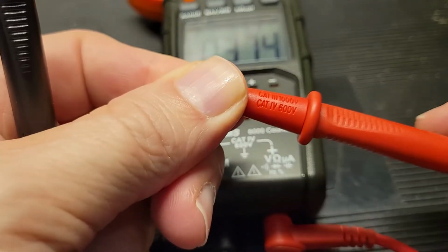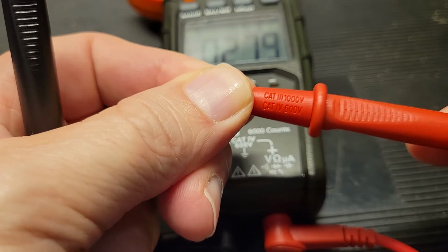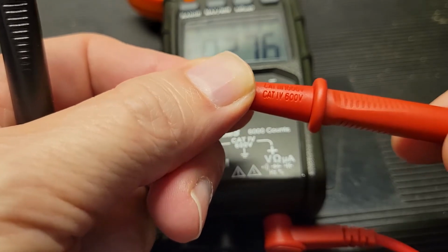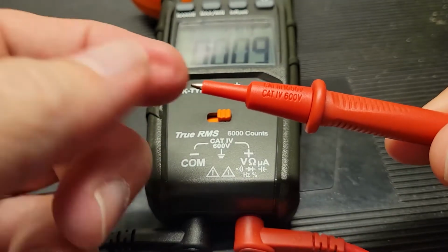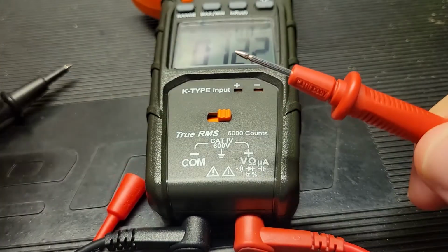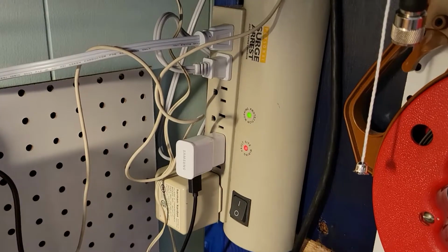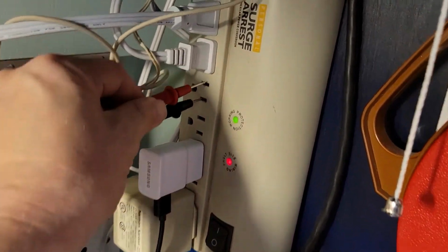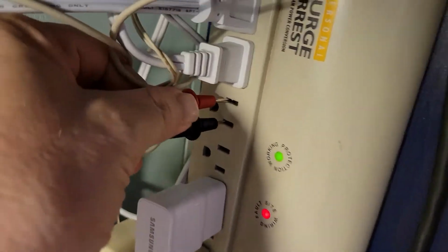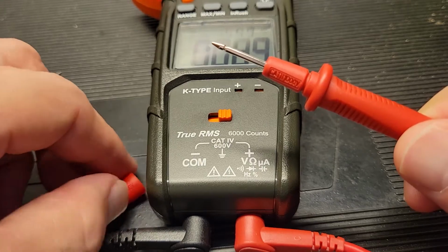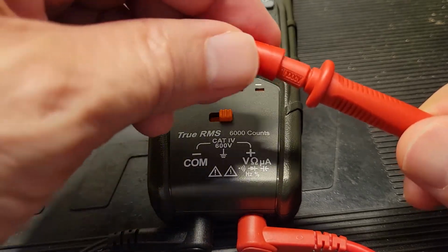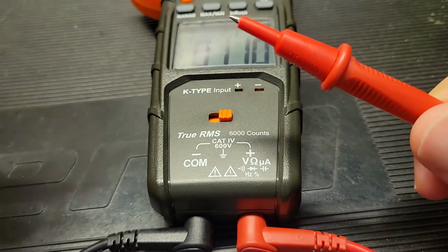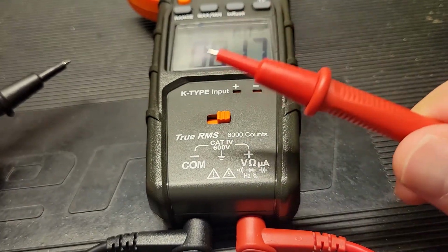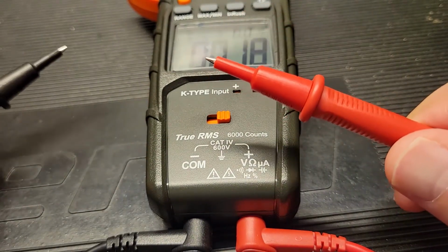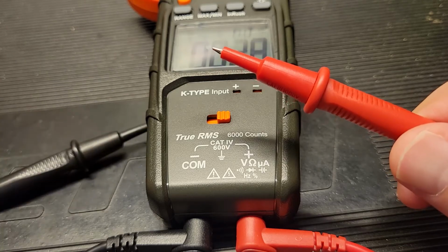The probes come with built-in shields that can be utilized in Cat 3 and 4 working environments. But if you're trying to work in a Cat 2 environment, let's say household outlets, you'll need to pull that shield off so that you can get the probes into an outlet so that you can get a reading. Just make sure that you reattach your probe once you're done. Otherwise, you'll lose them because there's no carrying case on the tool itself. You can always, of course, throw it into the bag.